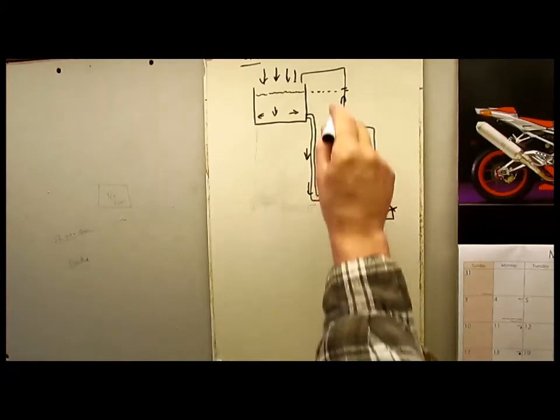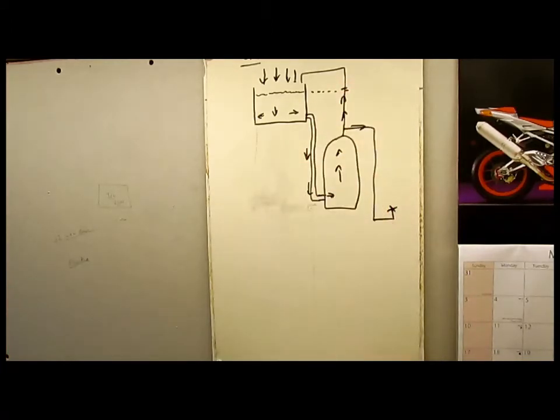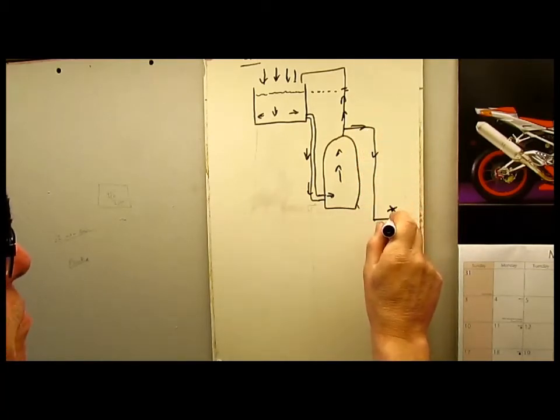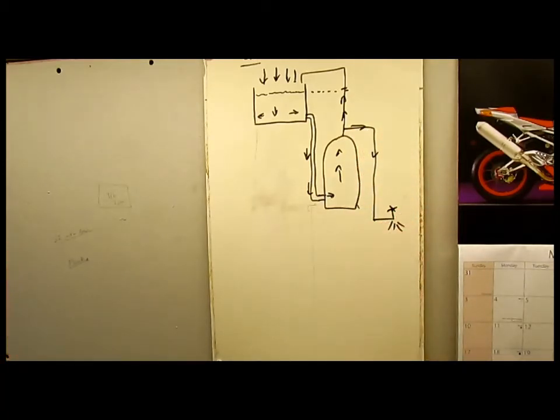Now it can't push any higher than that because the water is at that level, so it can't push any further than that. There's no pressure there because the water's pushing down that way, so it's pushing it all the way to the taps. When you open the tap then it comes, and that's why it's called gravity - it's gravity pushing down, it's totally reliant on gravity, there's no pumps, nothing. And that is a domestic hot water gravity system, it's as simple as that.